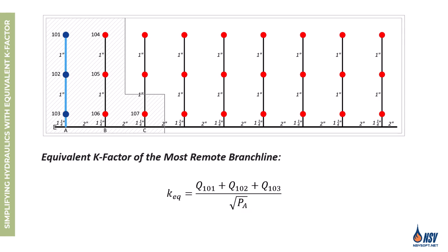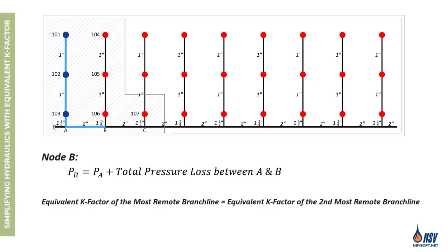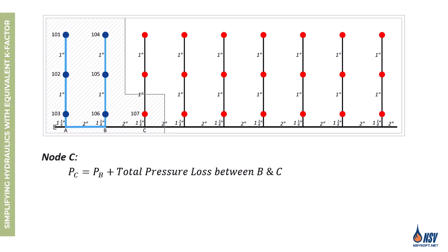With the pressure at node A calculated, we determine the equivalent K factor of the most remote branch line by dividing its total flow rate by the square root of the pressure at that point. In the next step we calculate the pressure at node B. The question then arises: how much flow will be discharged from sprinklers 104, 105, and 106 on the second most remote branch line? Rather than starting the calculation from sprinkler 104, we simplify the process using the equivalent K factor concept. Since the second most remote branch line is identical to the most remote one in pipe size, length, sprinkler count, K factor, and number of sprinklers in the design area, we apply the same equivalent K factor. With the pressure at node B known, we easily calculate the total flow rate for this branch line.